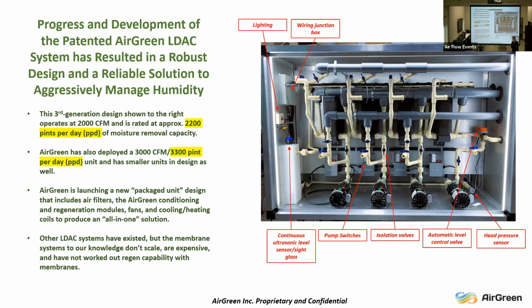One of the problems with Advantix is they didn't have visibility into their units until you cut it open. So we have a little polypropylene box that's tied in to our sumps, and an ultrasonic level, so we have continuous level measurement. Early on, say you're running a liquid desiccant system and the level starts dropping. Are you over concentrating or are you leaking? Don't know. We have fixed dimensions in here.